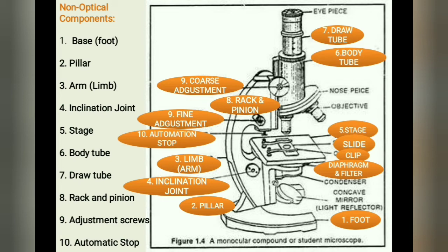The next part is the adjustment screws. There are two pairs of screws for moving the body tube in relation to the stage — larger for coarse adjustment and smaller for fine adjustment. In fine adjustment, the body tube or stage moves for extremely short distances. In coarse adjustment, the body tube or stage can move up and down. The coarse adjustment is meant for bringing the objective lens to a proper distance from the object so as to form an image at the ocular end. Fine adjustment is required to obtain a sharp image.